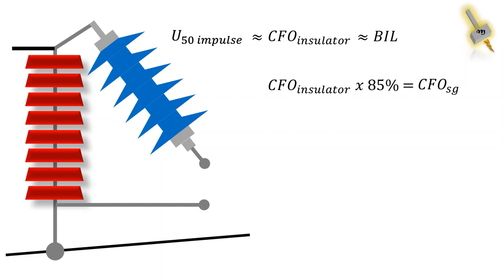Now from various electrode configuration, rod plane configuration has the lowest flashover voltage. So the CFO insulator shall be converted to CFO insulator in rod plane configuration. Now this is the gap factor for switching impulse. For getting gap factor for lightning impulse, the following formula is recommended. So the 50% impulse flashover voltage for rod plane configuration is this.